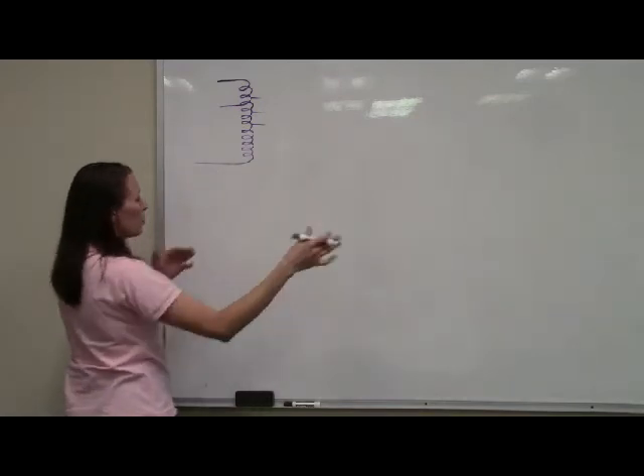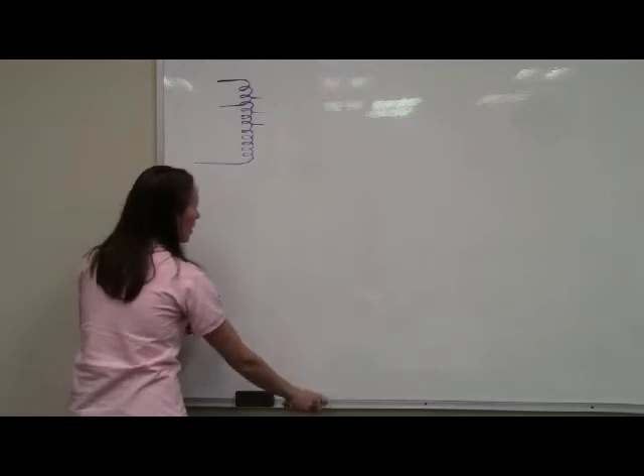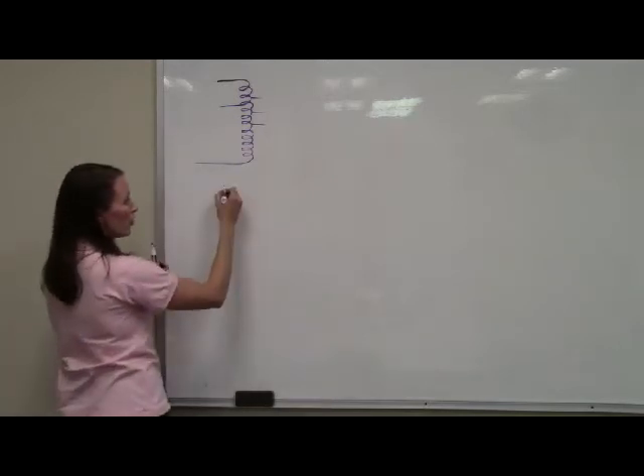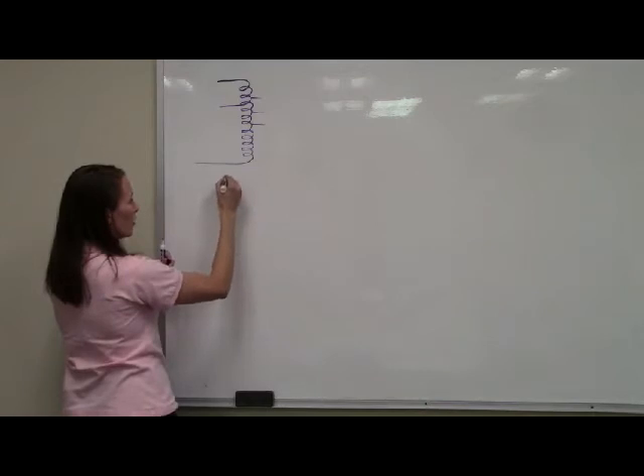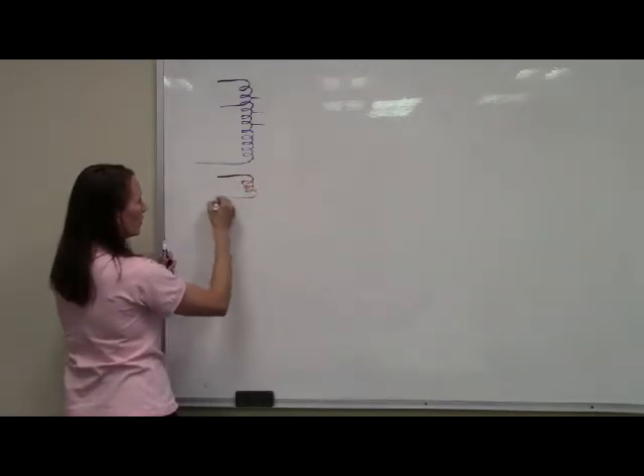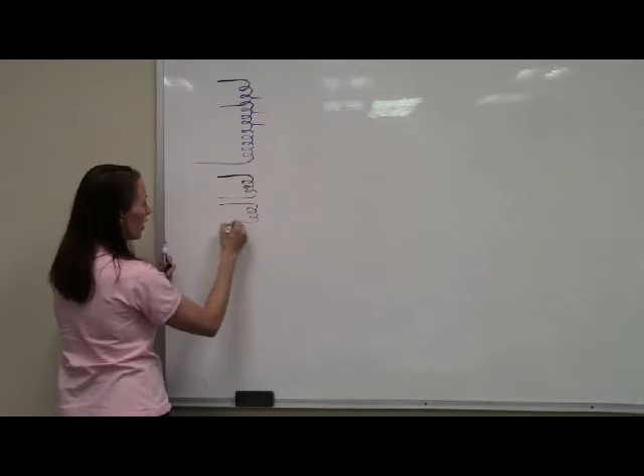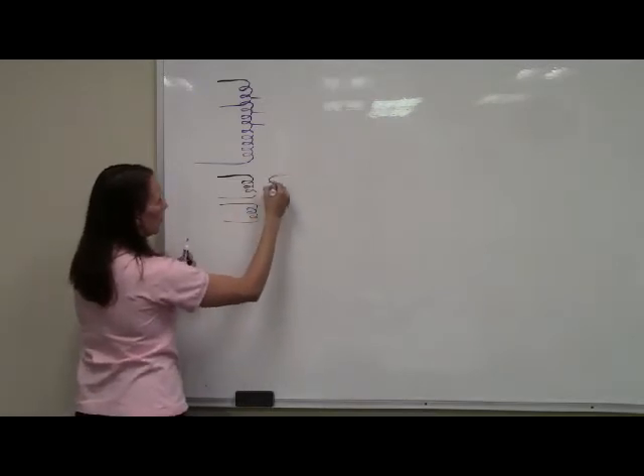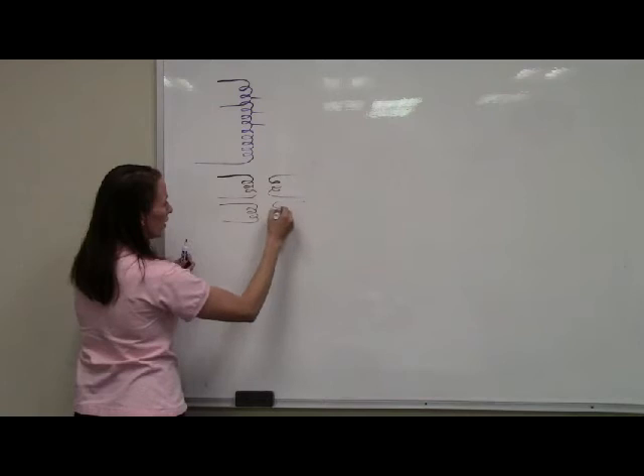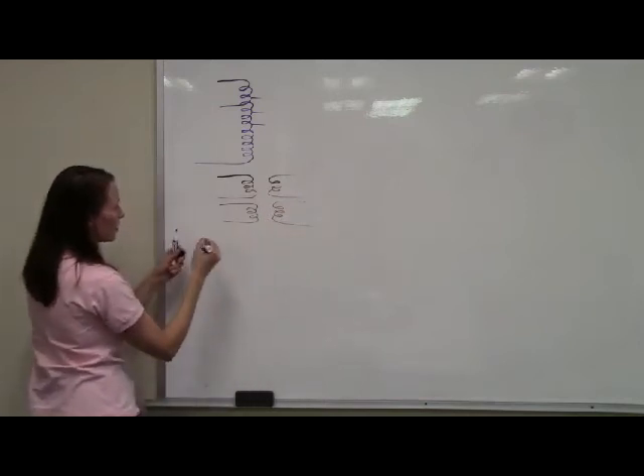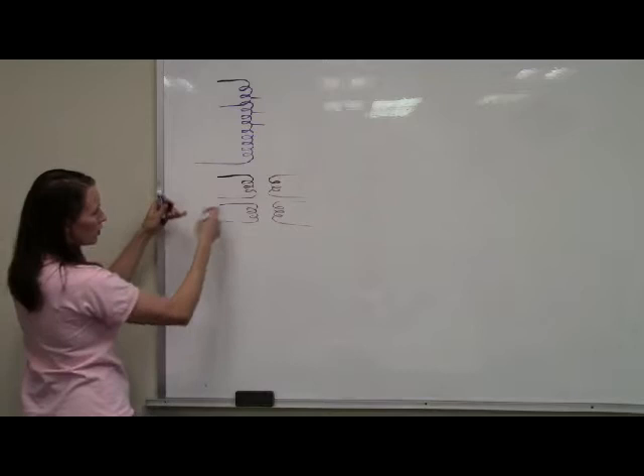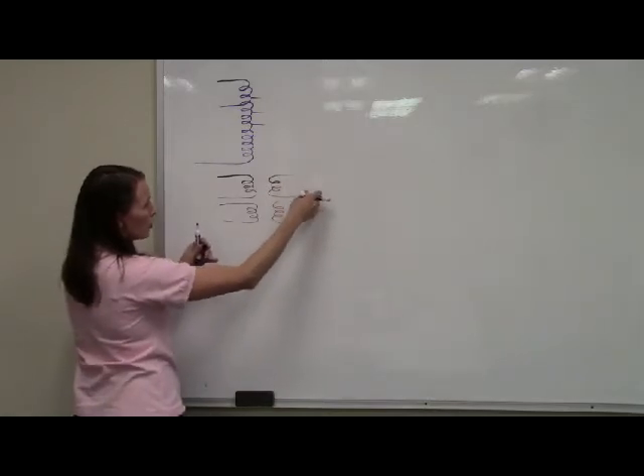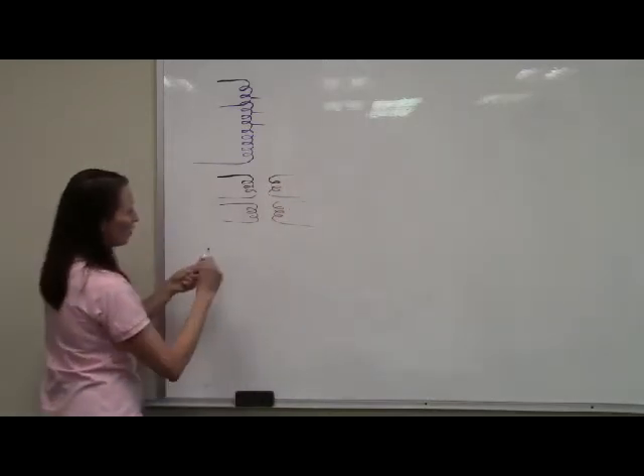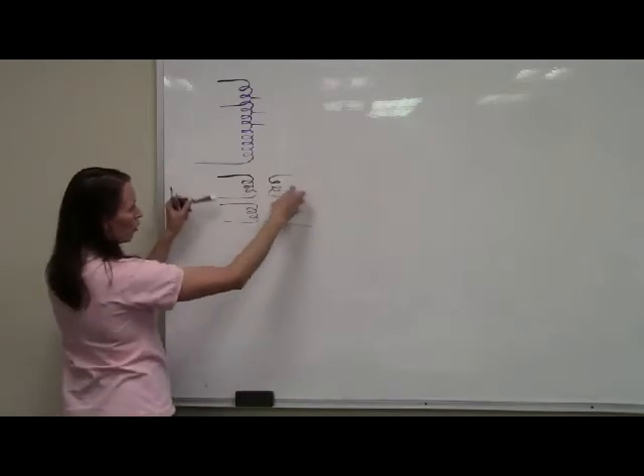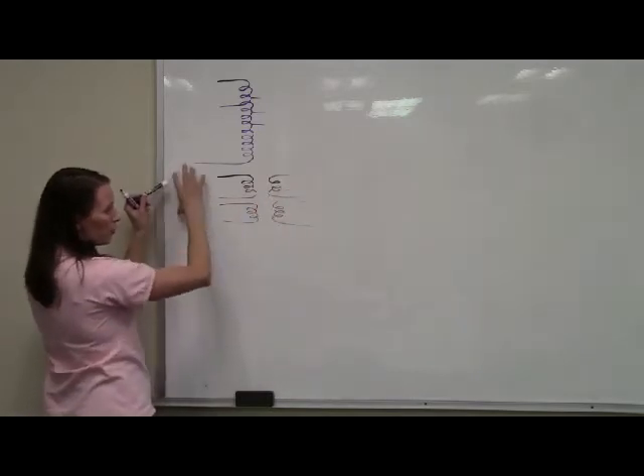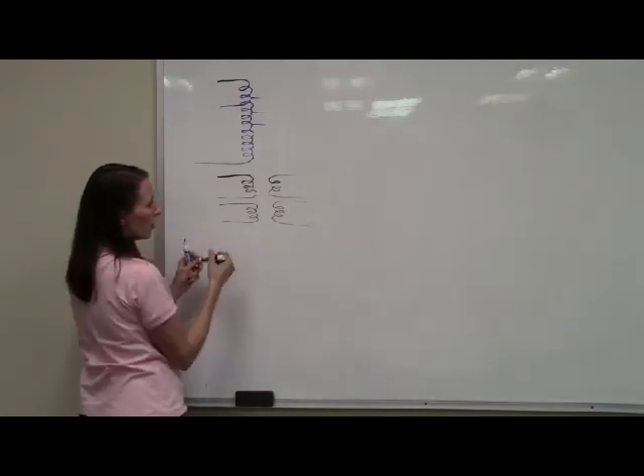to get the desired results. So you're a little bit familiar with a typical dual voltage single phase transformer, where you have your 2 primary windings and your 2 secondary windings. So you've got your X1, X2, X3, X4, and your H1, H2, H3, H4. And you know how to take those and hook them up to get the right voltage here and the right voltage here that you want.